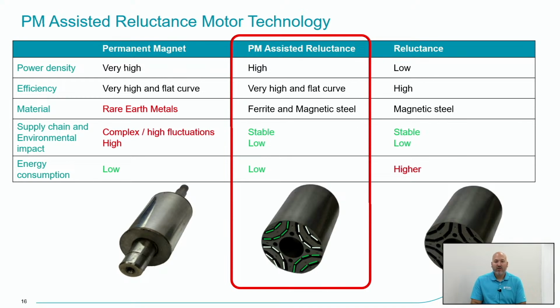So here's 3 different rotor designs. The first one on the far left is a traditional permanent magnet rotor. So that whole thing there would be that neodymium material. As I touched on earlier, supply chain can be very complex. There could be high fluctuations in cost and availability. There's also a very high environmental impact with it being toxic. However, the benefit with that is you get much lower energy consumption or those higher efficiency levels we were talking about at IE5 rating. The far right is a typical induction or reluctance one there.